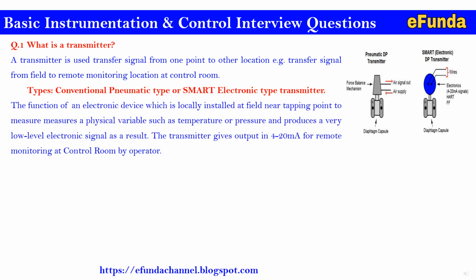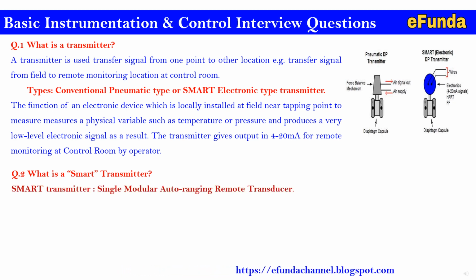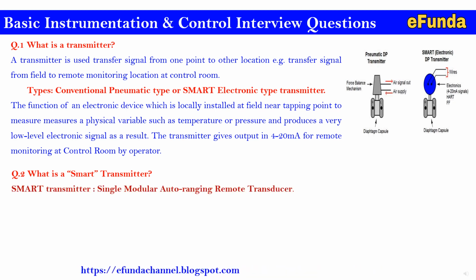The function of an electronic device which is locally installed in the field near the tapping point is to measure a physical variable such as temperature or pressure, and it produces a very low level electronic signal as a result. The transmitter gives output in 4 to 20 milliamp for remote monitoring at a control room by the operator. Question 2. What is a smart transmitter? A smart transmitter is a single modular auto ranging remote transducer. A little bit difficult to remember, but by practice you will remember it as you are practicing on or working on such types of devices.